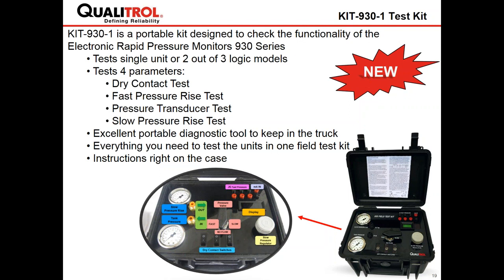There are 4 different test parameters. There's dry contact test, fast pressure rise test, pressure transducer test, and slow pressure rise test. It's an excellent portable diagnostic tool that can also be kept in the truck, similar to the previous one. Everything that you need in one case, and the instructions are also right on the lid of the case for ease of use.